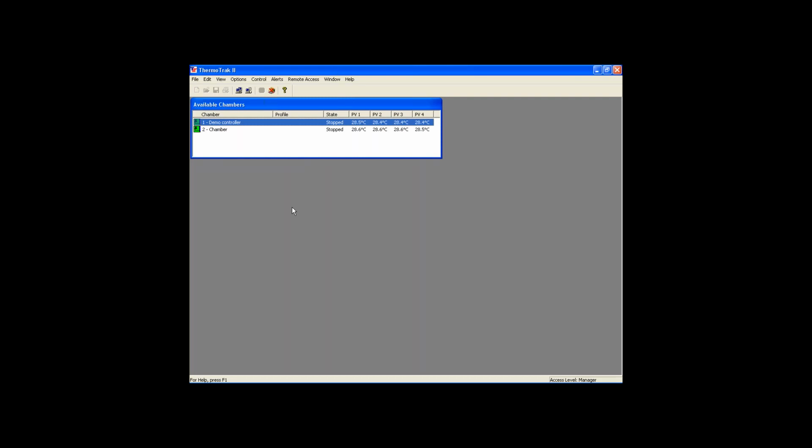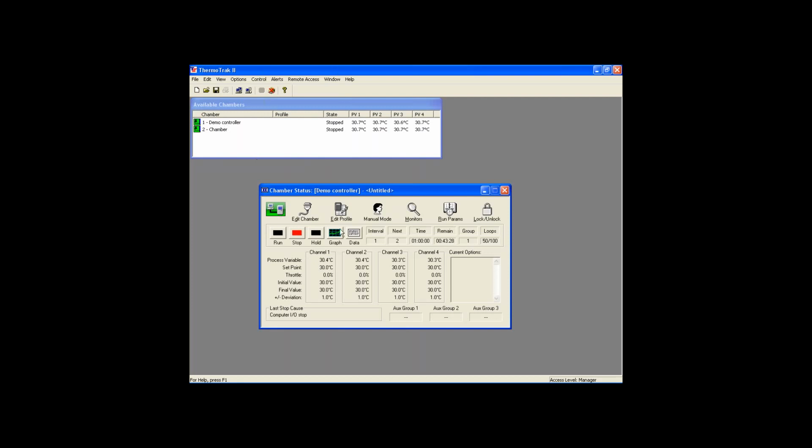If you have a lab with different controllers in it, so you have a handful of 8800s, some 3200s, maybe some older 7800s or 6850s, then ThermoTrak is generally the way to go because some of those older controllers or more basic controllers don't have VNC capabilities. And with these, you can still certainly stop and start chambers, write profiles, but to be honest, it's a software that was written over a decade ago, so it's a little bit antiquated. So if you do have the ability to use VNC with all 8800s, generally the nicer way to go.